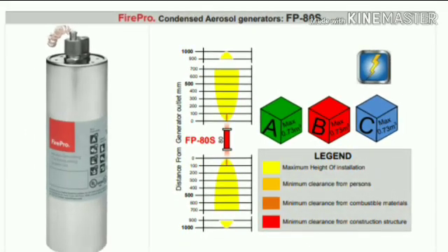Next generator is FP-80S. Activation line supervision current maximum: 5 mA. Aerosol discharge time: minimum 5 seconds, maximum 10 seconds. Number of discharge outlets is 2. Generator dimensions: height 185 mm, diameter 51 mm. Self-activation temperature of FPC: 300 degrees. Class of fire: NFA 2010 ABC. Generator coverage constraints: minimum height 0.45 m, maximum area 2.12 m², maximum throw 1.06 m. Maximum height of installation: 2 meters. Minimum clearance from person: 100 mm. From combustible materials: not required. From generator casing: 6.4 mm.